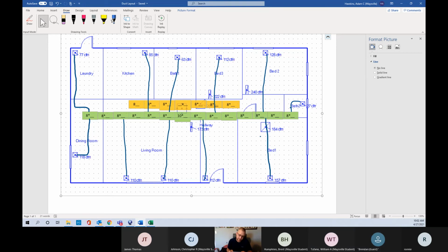But if you go too big with your duct, I have run into this with one system where the duct was really oversized, and I didn't think I was going to be able to move enough air because it slowed everything down. They had an old PSC motor which would just move the right amount of air, and I put in a variable speed motor, and when you put in that variable speed motor, it'll only move a constant volume.